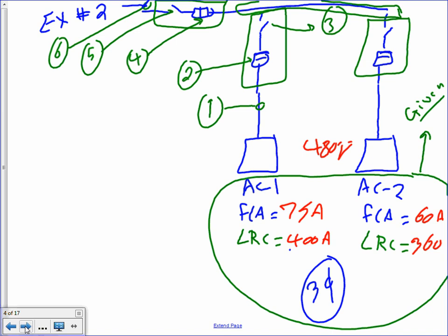Controller and overload. We can do the controller overload like motors. The only thing that we missed them because 99% of the time, guys, the controller and the overload is specified by who? The manufacturer of the equipment. So we're really just providing this fuse disconnect for them. So that's why what you're providing here is just a fuse disconnect. A fuse disconnect. Any questions about the given?